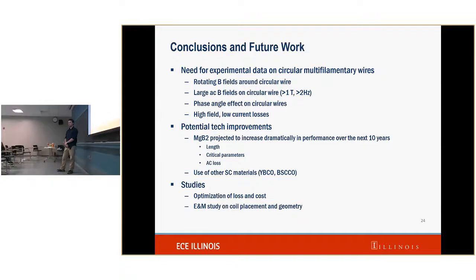But then you said that you were optimizing this for 20 Kelvin? Yes. Okay, so why that difference? A lot of that was due to the choice of the superconductor that I had. Niobium-tin is one of the more common ones at 4 Kelvin, but the heat load at 4 Kelvin is enormous compared to any heat load that you'd have at 20 Kelvin. Niobium-tin can't go above 14, so I would need to choose something else. Basically, for any AC application, I can't operate below 20 unless I want some massive load on my cryogenic system.